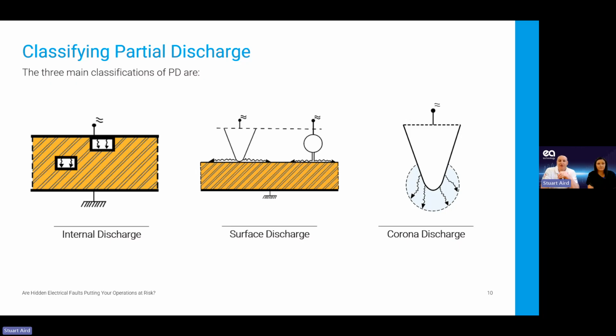If you've got a little air pocket within there, that's got a completely different dielectric strength to the material around it, whether that's resin or anything like that, which would be a lot stronger. So you start getting these high electrical stresses in the air pockets, and they discharge. Every cycle we're getting a little discharge within this air pocket, and that will cause partial discharge, and the void will microscopically be getting bigger every time that happens, and it will lead to failure over time. So we can trend that over time.